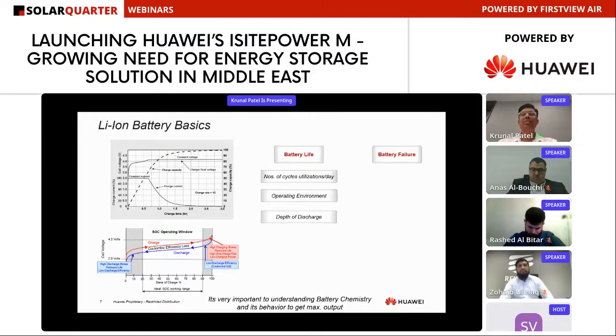Then third is the depth of discharge - how much should I discharge the battery? Should I discharge it 100%? Should I discharge it at 80% or 60%? This is also defined and has to be maintained to increase the life of the battery. Then there's the C rate.